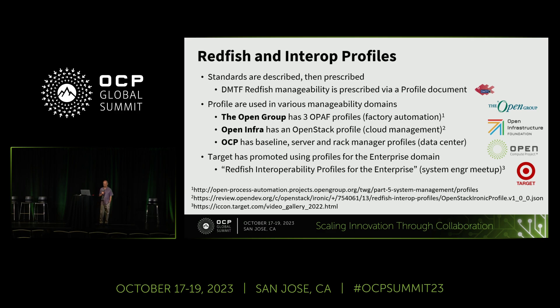OCP has specified Redfish as the manageability interface for the platforms. In specifying it, you can write a whole bunch of requirements, but requirements exist in documents and documents are hard to read. Redfish actually created the concept of profiles — JSON formatted files that can be used to auto-generate tests and test a conforming implementation. The DMTF is what I call a descriptive standards body; their job is to extend Redfish into as many management domains as possible, from the data center to the edge.